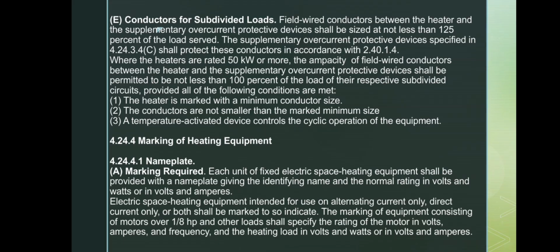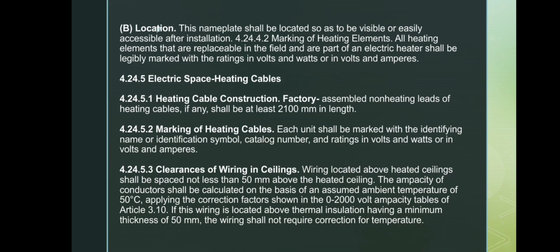For marking requirements, every fixed electric heater must have a nameplate showing the brand and its electrical rating, either volts and watts or volts and amps. If it is AC only, DC only, or both, that must also be shown. For heaters with motors larger than 1/8 horsepower, the nameplate must list the motor voltage, amperage, and frequency. Next, the nameplate must be placed somewhere visible and easy to access after installation. All replaceable heating elements must be marked with the voltage and watt or amp rating.